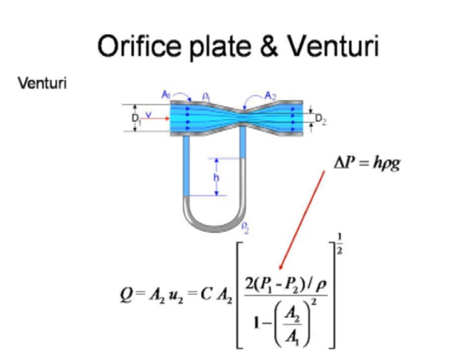Of course, we can now substitute in for p1 minus p2, the pressure difference, and we can substitute in the equation depth times density, the static head equation. If we do that, we can then cancel the density terms out, but that sort of hides a secret, because if we do that, bearing in mind the density in the square brackets has come from Bernoulli's equation, that's the density of the process fluid, the fluid flowing through the venturi or the orifice plate. So really if we do that, that gives us the pressure measured as a height of process fluid, normally liquid, flowing through the system.